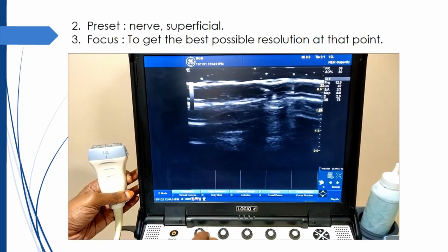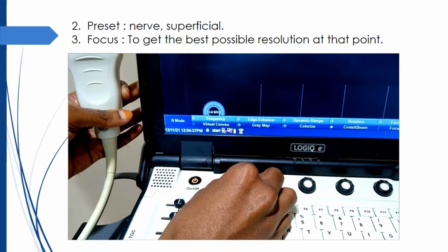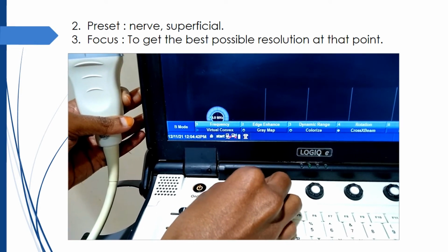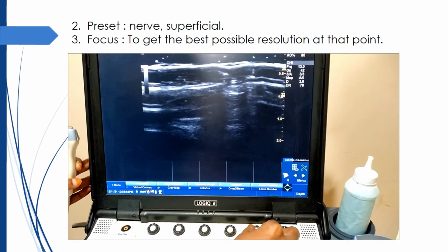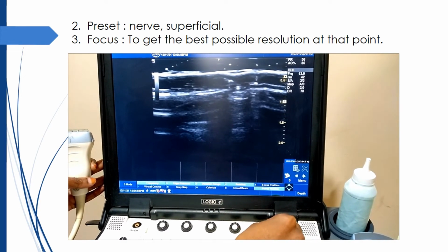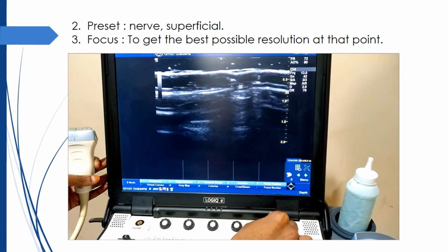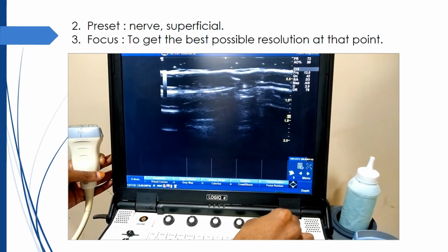Even with the selected probe, further there's an option to choose the frequency. Here it is between 13 MHz to 8 MHz. In pediatrics, I will choose the highest available frequency. So here I'll set it at 13 MHz. And choose the focus number and position depending on the depth. For a depth of 2 cm, GE Logiq provides a maximum of 2 focal points. Now I have set it at 1 focal point and note the change in the image as the focal point is adjusted.